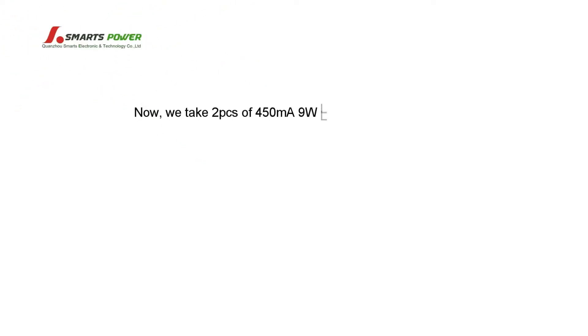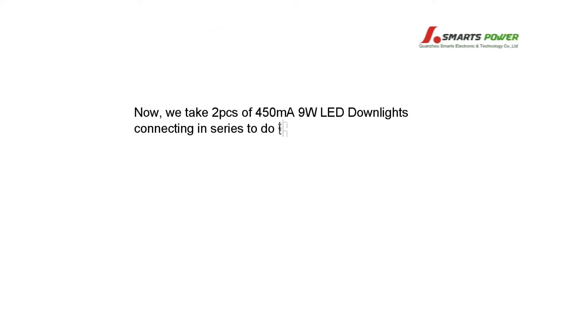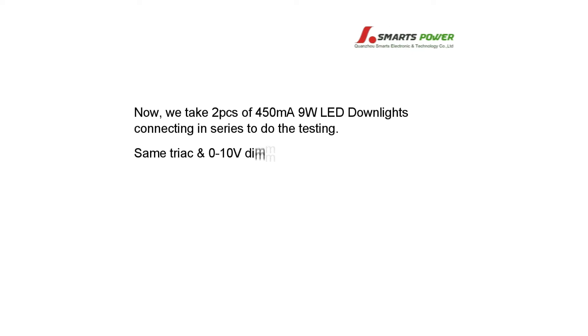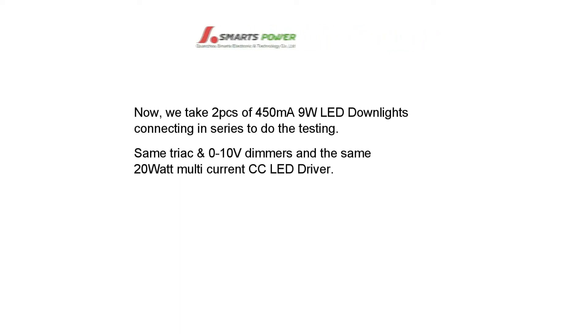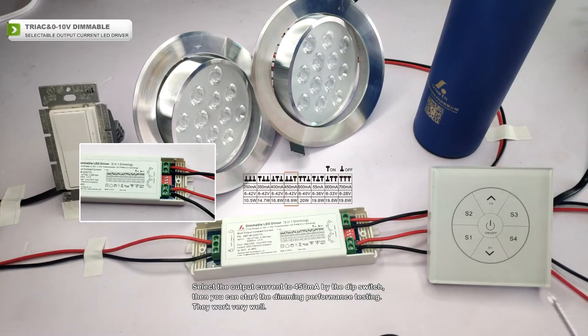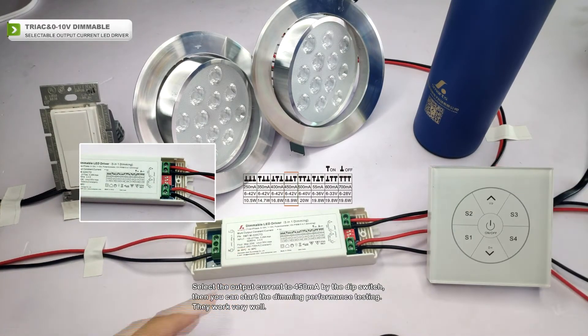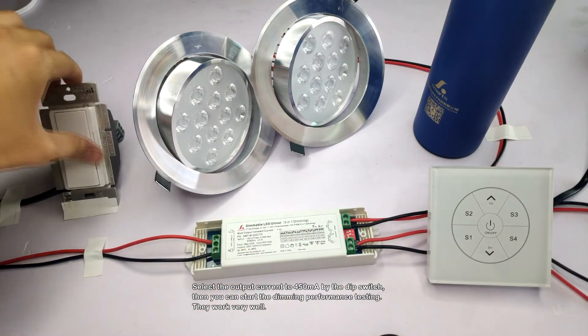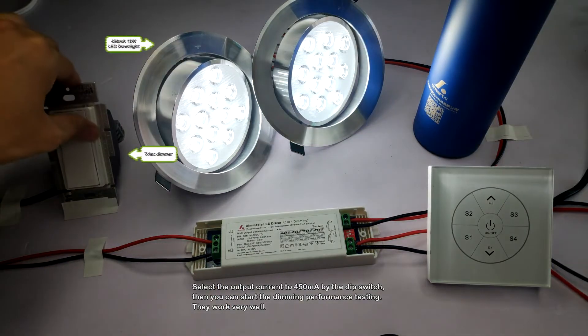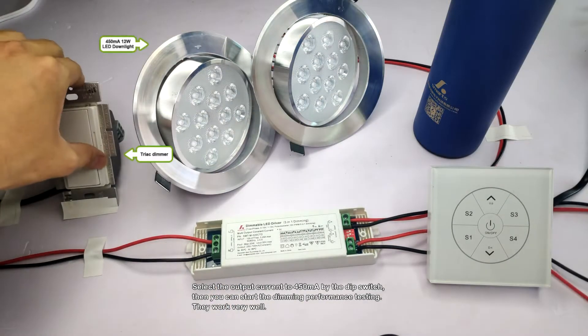Now we take two pieces of 450 mA 9 watt LED downlights connected in series to do the testing, using the same triac & 0-10V dimmers and the same 20 watt multi-current constant current LED driver. Select the output current to 450 mA by the dip switch, then start the dimming performance testing.